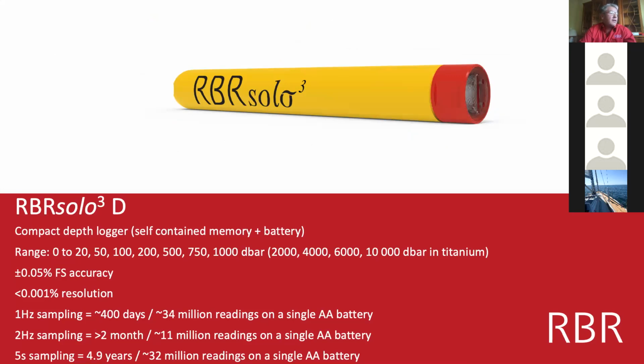For the logger, we have the 0 to 1000 dbar, with a plastic housing, specific plastic. And then we move to the Solo Depth, with a titanium housing for 10,000 dbar maximum. We are providing high accuracy and higher resolution for this type of sensor.